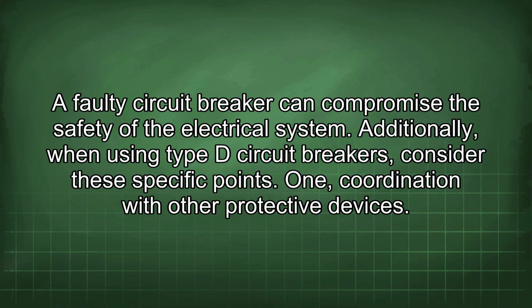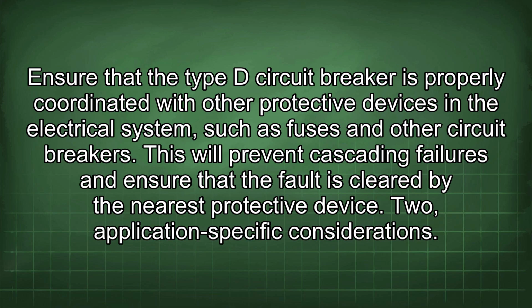1. Coordination with other protective devices. Ensure that the Type D circuit breaker is properly coordinated with other protective devices in the electrical system, such as fuses and other circuit breakers. This will prevent cascading failures and ensure that the fault is cleared by the nearest protective device.